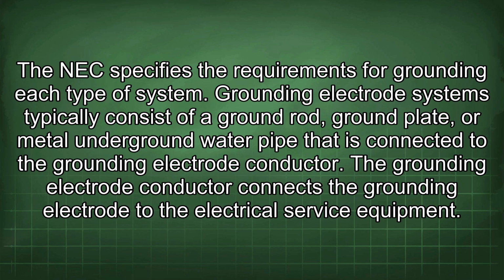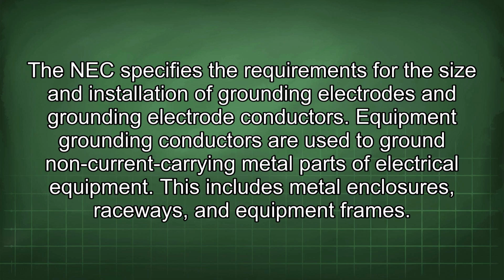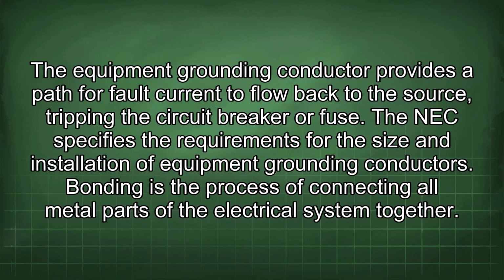Grounding electrode systems typically consist of a ground rod, ground plate, or metal underground water pipe that is connected to the grounding electrode conductor. The grounding electrode conductor connects the grounding electrode to the electrical service equipment. The NEC specifies the requirements for the size and installation of grounding electrodes and grounding electrode conductors. Equipment grounding conductors are used to ground non-current carrying metal parts of electrical equipment. This includes metal enclosures, raceways, and equipment frames. The equipment grounding conductor provides a path for fault current to flow back to the source, tripping the circuit breaker or fuse. The NEC specifies the requirements for the size and installation of equipment grounding conductors.